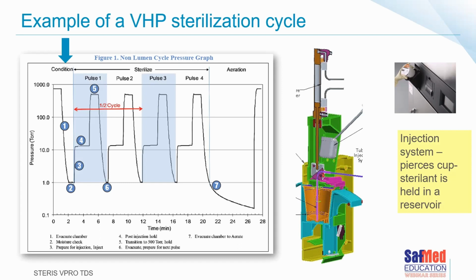The sterilant had been drawn up from the cup but held in the reservoir until the moisture level is correct. If the moisture level isn't correct at this point, the machine will, in this particular instance, cancel or abort the cycle, but not having actually injected the sterilant. So that conditioning phase generally helps us reduce the number of aborts from residual moisture because it gives a little extra vacuum and hopefully tries to dry what's there. If that all fails, of course, we have to unpack and start the process all over again with that device. It officially needs to go through the cleaning, repacking process. So we'd like to try to avoid those kind of aborts.